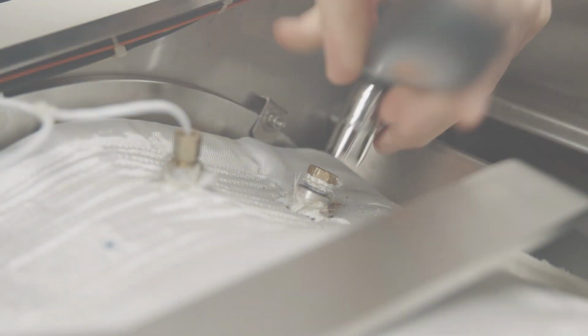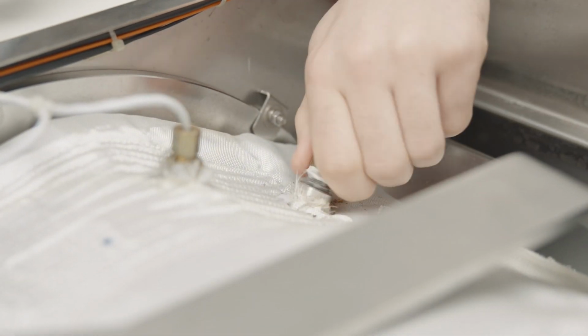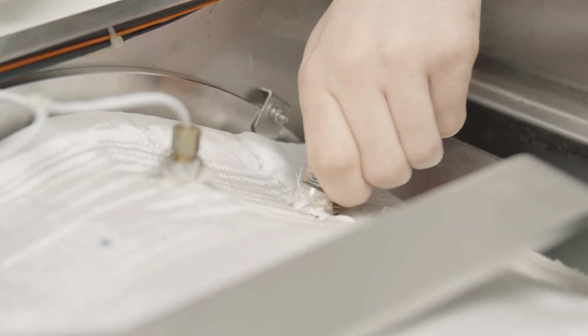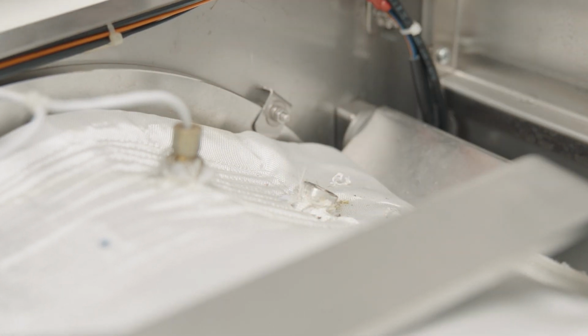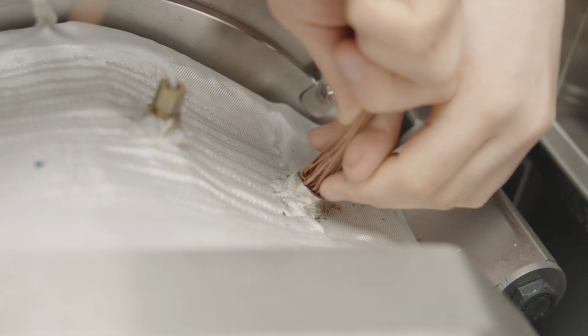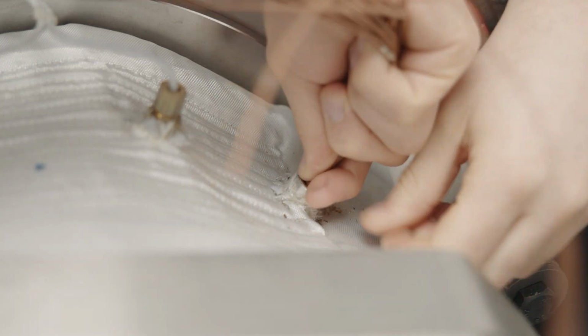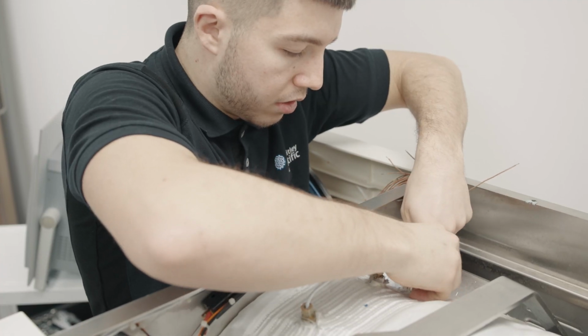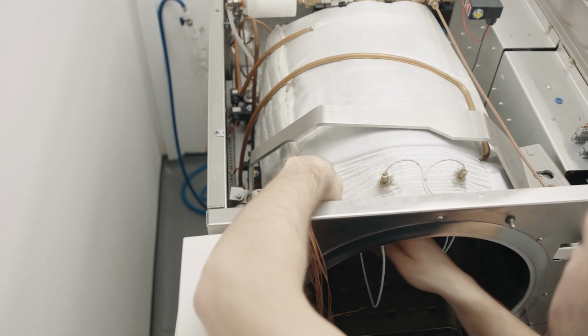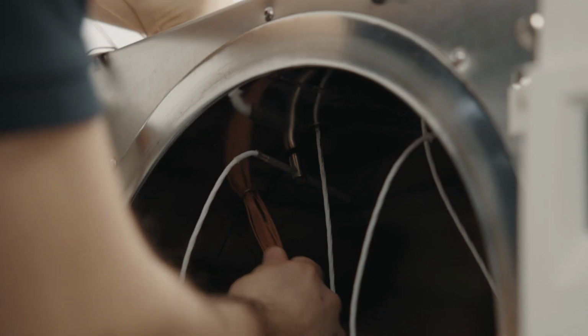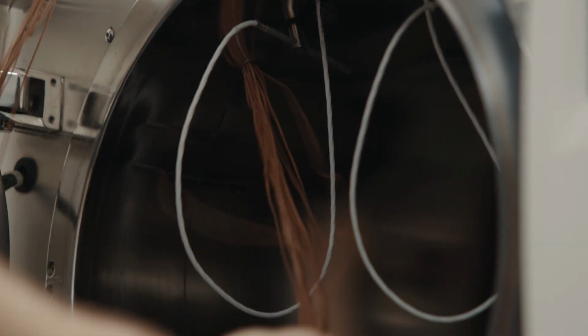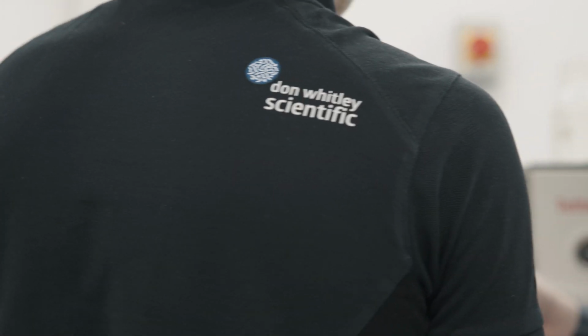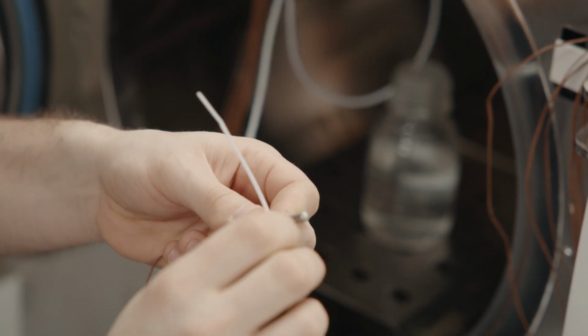Calibration of the autoclave ensures that it is performing correctly. The act of calibration is to measure or compare a value against a known standard. Using the example of an autoclave, we would look to compare any value given by the temperature probes within the autoclave with the values provided by our test equipment during sterilization. In addition, we also compare the sterilization time displayed against a calibrated stopwatch.